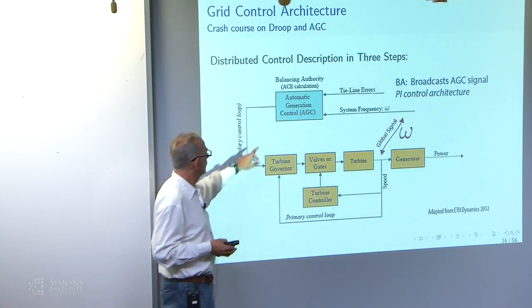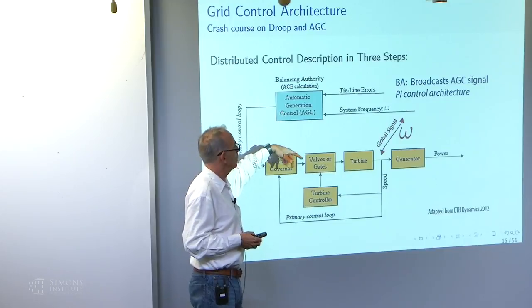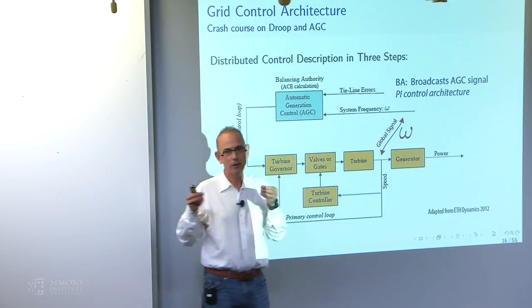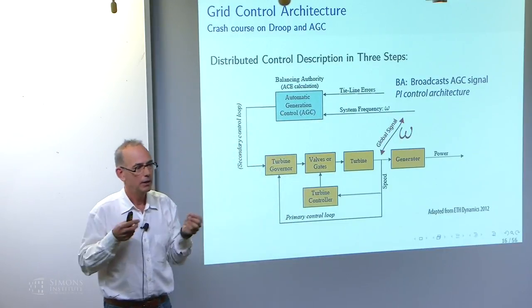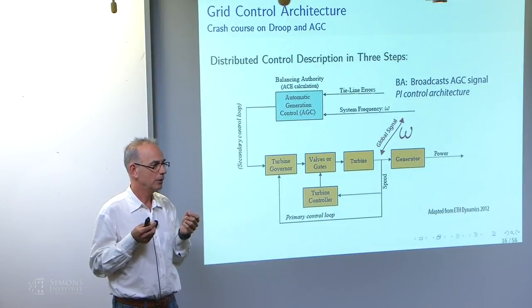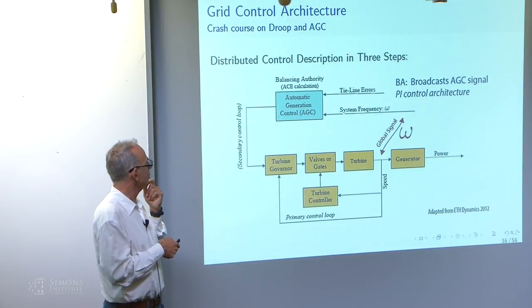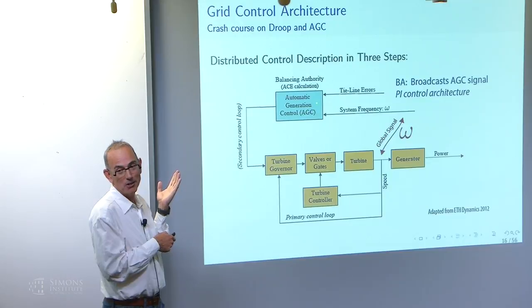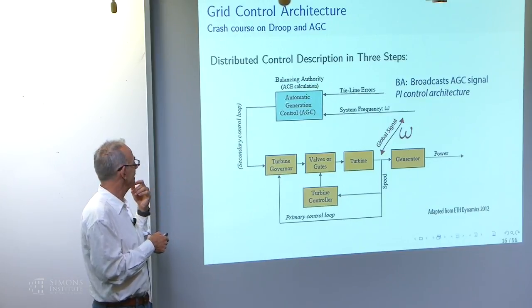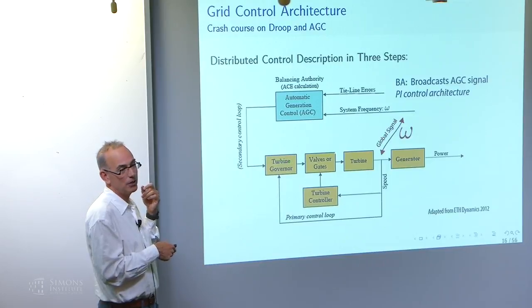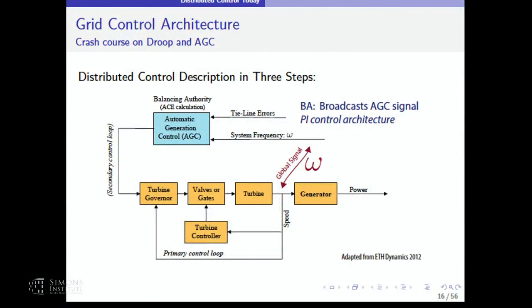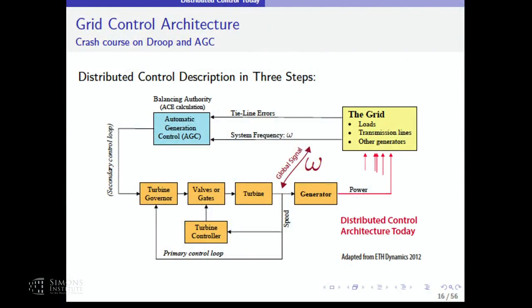Then you've got the balancing authority, which measures tie line errors - the error between what was scheduled and what was actually flowing between balancing authorities. System frequency goes through a PI controller, thank you Richard Murray, and then sends that to every generator. They're all getting the same signal, scaled.